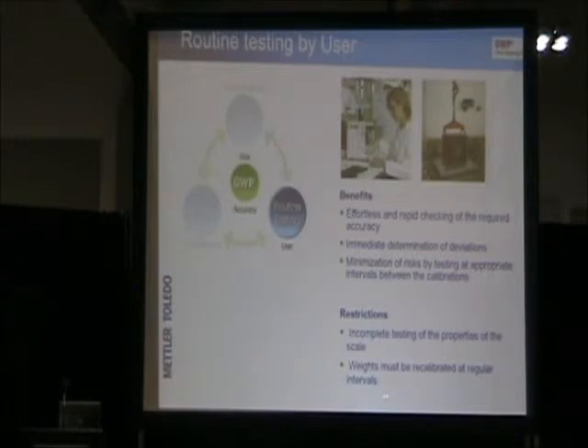The last part here is routine testing, which is you guys at your facility. Routine testing allows you to very quickly see the actual accuracy of your balance before you do any important or critical application, and it minimizes the risk by testing at appropriate intervals between your calibration cycles. The restriction is that you're not testing all the different parameters of uncertainty, and it's usually just a quick check to ensure that you yourself are in compliance. These also have to be sent out for recalibration at a regular interval.